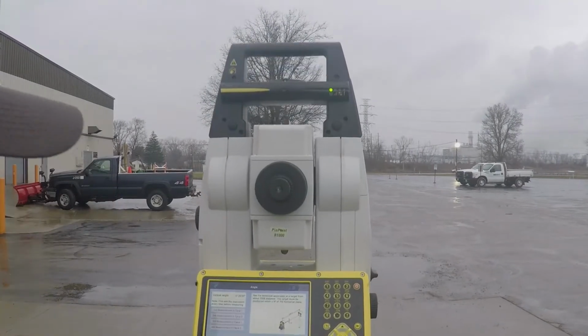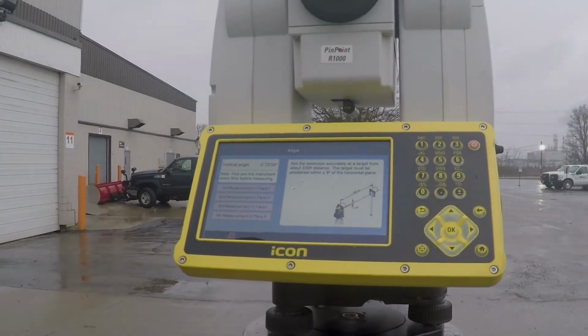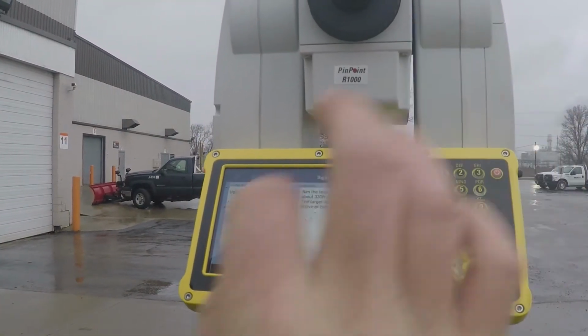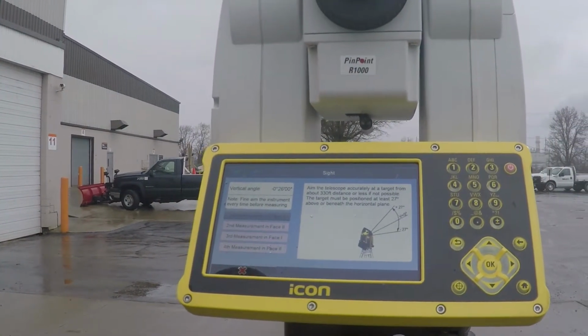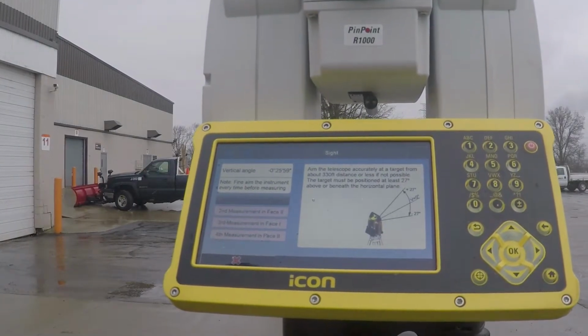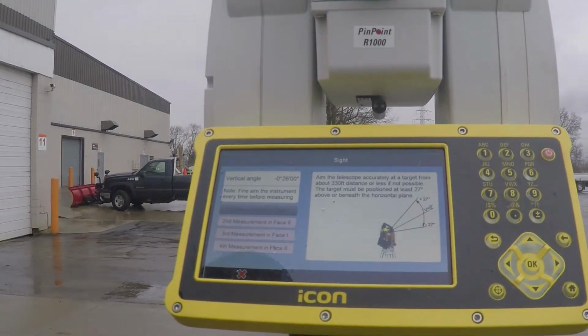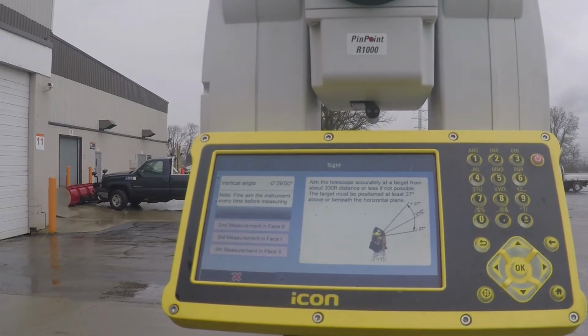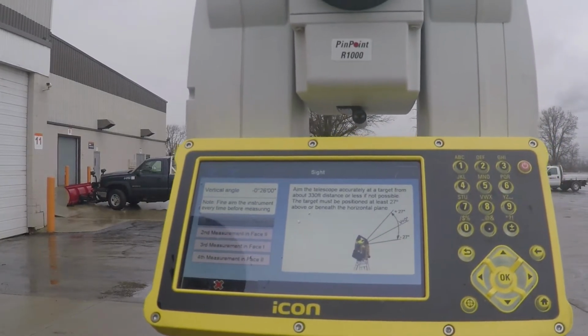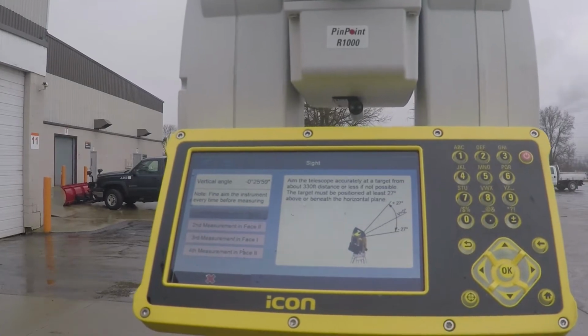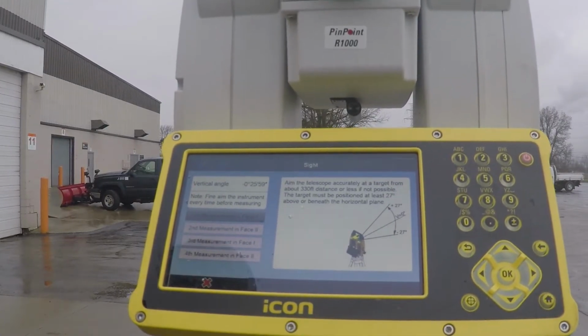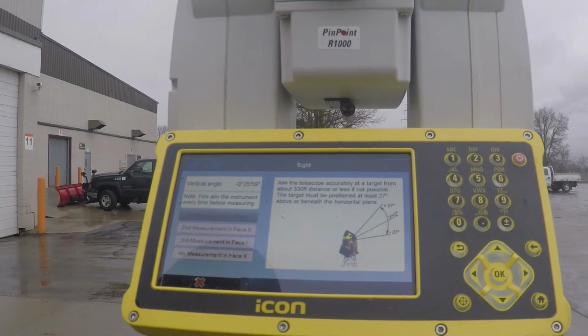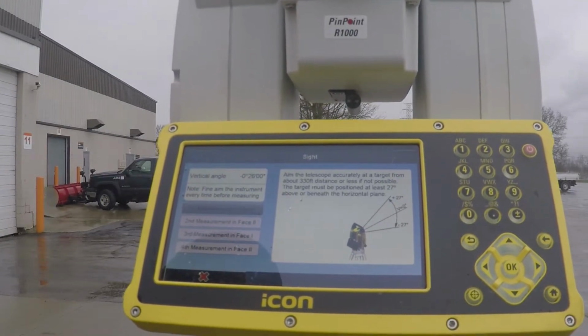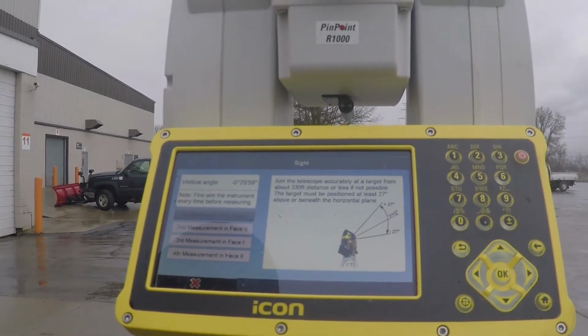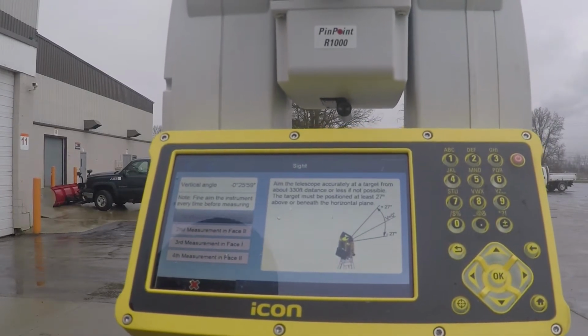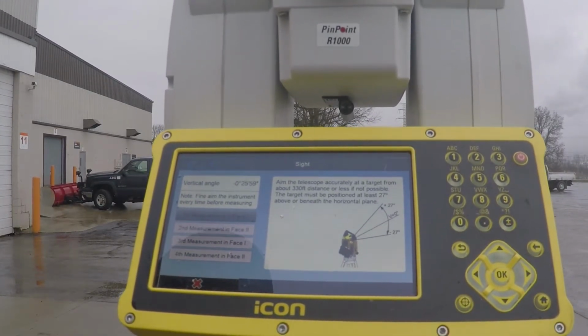So once we get through our 4th measurement, blue dot on the upper right hand of the screen, that's going to advance, and now we're going to do the vertical angle. And it's essentially the same thing. It doesn't have to be a prism. So we're right next to a building here. We're kind of in an urban setting here with nothing real too tall to sight. So we're just right up against a building here. But the rules say aim the telescope accurately at a target from about 330 feet distance or less if not possible. The target must be positioned at least 27 degrees above or beneath the horizontal plane.